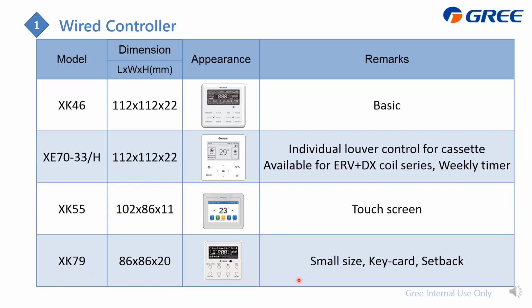For this one, compared with the basic one, it is small in size, and it also has the key card function, which means if you stay in a hotel, we allow you to insert the card, then you can turn on the indoor unit. If the card is taken out, there are 2 options. The first is to turn off the indoor unit, the other is to apply the setback function. Later I will explain this function in detail.